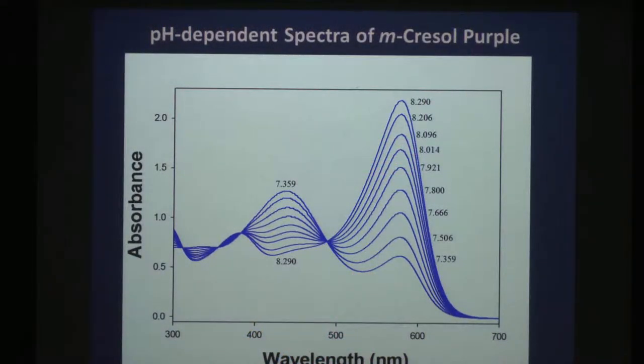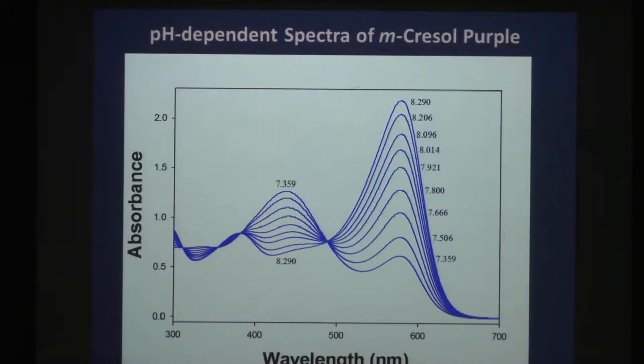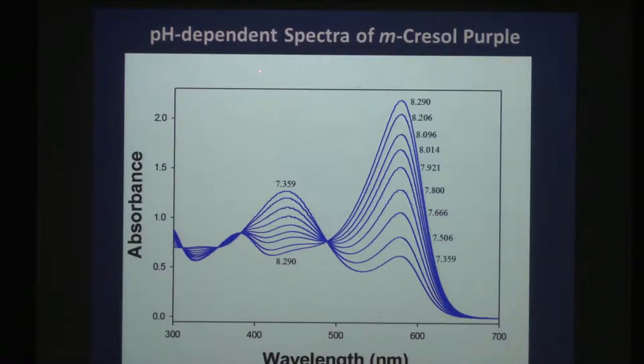You saw what the eye sees when viewing these various colors; this is what a spectrophotometer sees. In practice we utilize only three wavelengths: one at the peak, one at another absorbance maximum, and one further out as an extra check for baseline changes in the spectrophotometer. If you were to map a particular color onto this diagram it would essentially appear as a narrow vertical line.